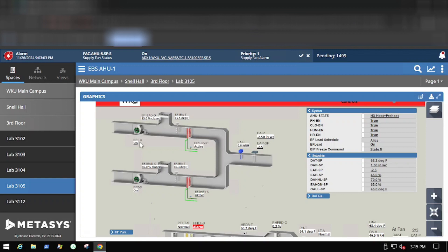The exhaust fans are both constant volume — they run at the same speed regardless of conditions. The way we maintain the negative set point in the exhaust system is by manipulating relief dampers. If many people raise the sashes on the hoods at once, it might bring the pressure up slightly, so the damper closes down to allow a little more vacuum to be pulled. Conversely, if everyone closes the hoods and pressure drops further negative, the damper opens to give a little relief to the fans.